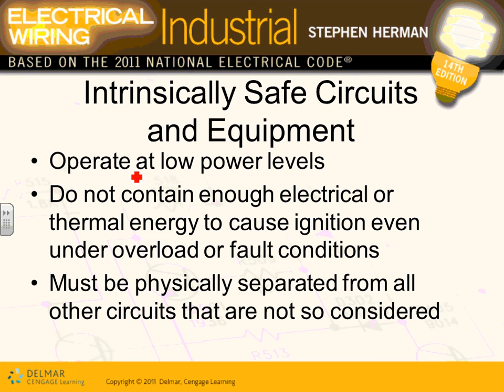So these intrinsically safe systems, they use them for instrumentation, sensors and alarming systems inside all the hazardous locations. So it can tell you what's going on: temperature, pressure, all these sensors. If there's a short circuit in that sensor, it wouldn't ignite. Does that make sense? They operate at low level energy that does not ignite. They do not contain enough electrical or thermal energy to cause ignition. They don't ignite under abnormal conditions, overload, or fault. So if you overload that circuit that goes to the sensor, it doesn't have enough energy. Even if you short them, grabbing a hot and a neutral and touching them to each other, you wouldn't get an ignition.